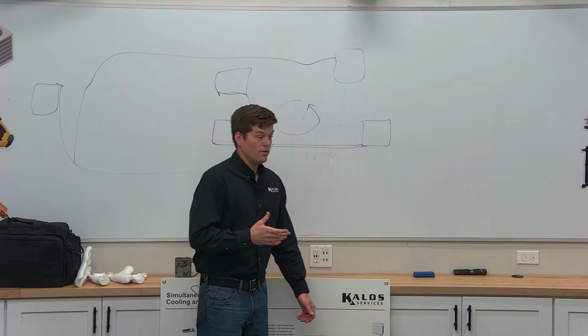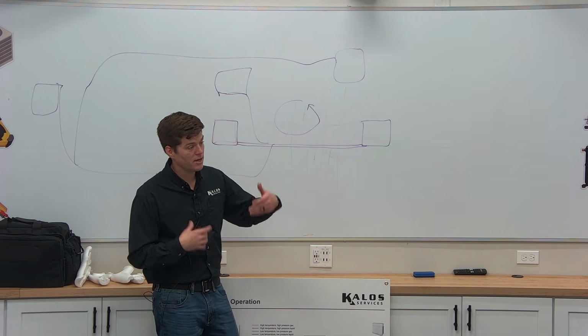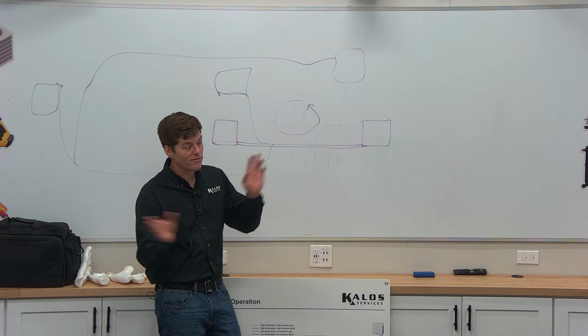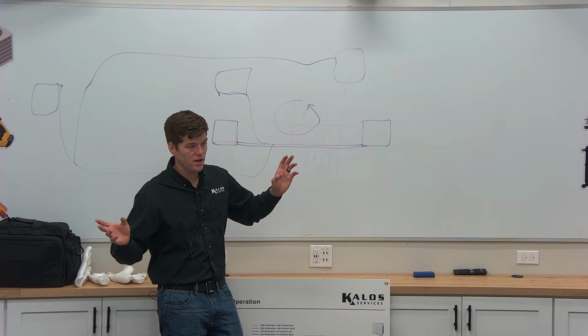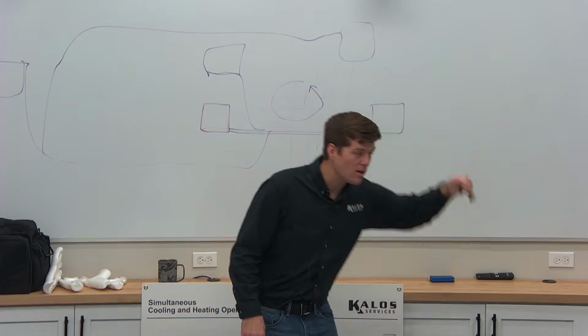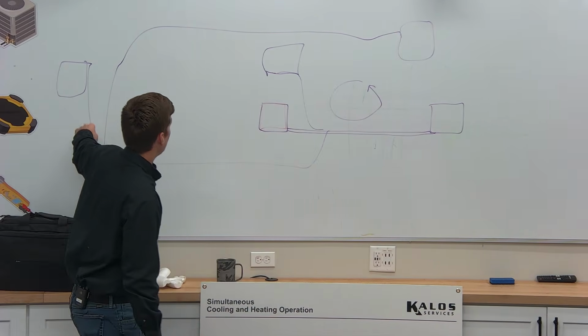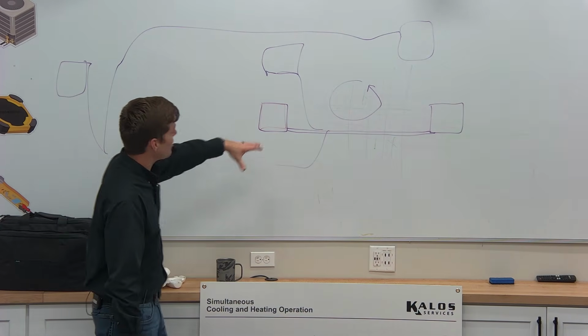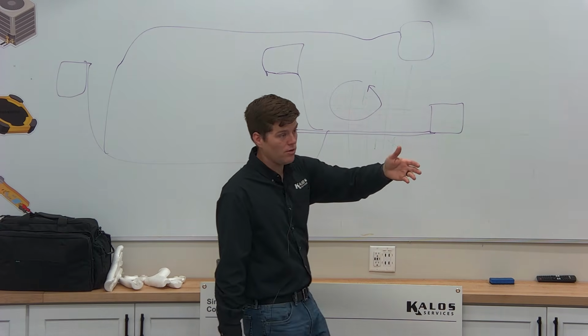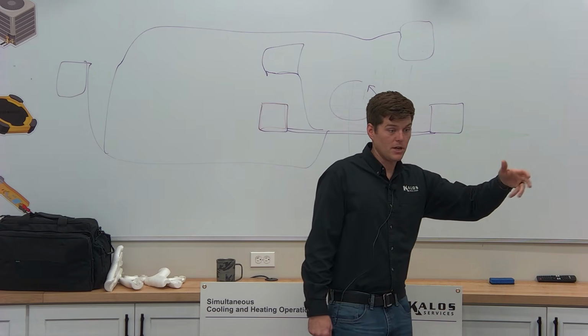You're going to get oil trapped in specific fan coils. You're going to get capacity losses. It's going to literally sling it everywhere. It's going to go every which way. And you'll find that if that happens and it's horizontal like this, and then it goes down to a unit that's below other units in general, that fan coil, when it's off, is going to pool oil in it.